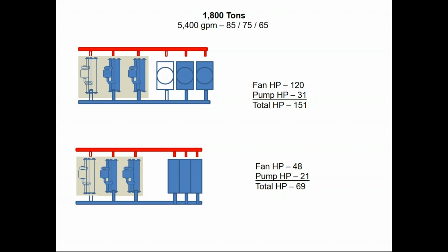Traditionally, on a tower system, as you turn a chiller off, you turn a tower cell off because we have less flow and it can't handle reduced flow in the system. So in this case, their fan horsepower is 120. The pump horsepower is 31 for a total horsepower of 151.